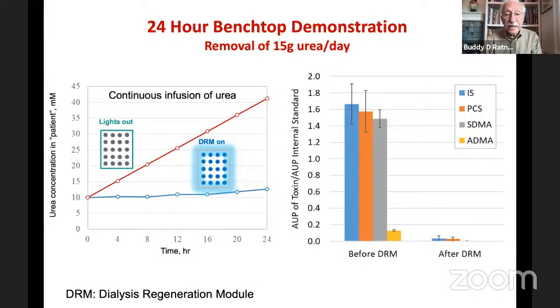How does it work? Well, here's some real data. On the left, you can see the experiment. What we're doing is continuously infusing urea into a tank at about the same rate your body makes urea a day. This would lead to about 15 grams of urea added into the tank during the day. And with the lights out on the DRM, the dialysis regeneration module, you can see the red curve, the urea concentration is steadily going up in the tank. Why? Because we're adding urea. When we turn the dialysis regeneration module lights on, see the blue curve, the urea concentration of the tank is remaining relatively quite steady. Again, that urea is being turned into nitrogen and CO2.